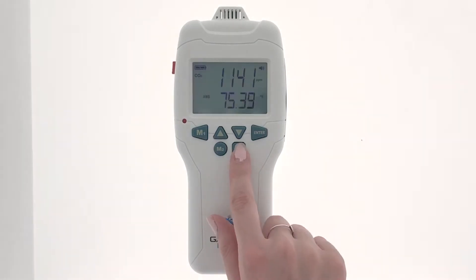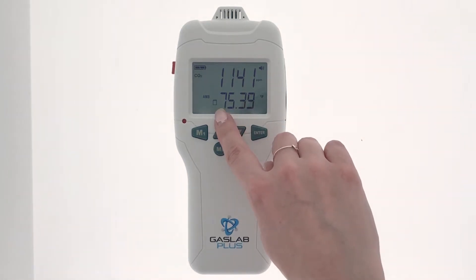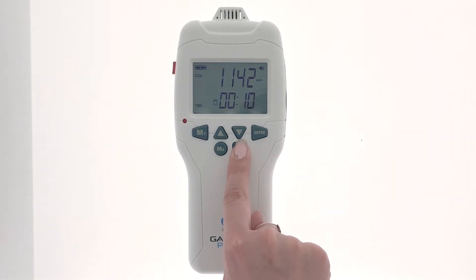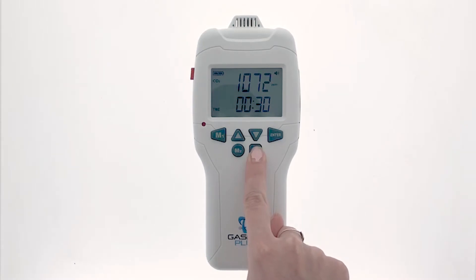You've got a 16 gigabyte SD card that comes with it to fill with all of your data — and trust us, that is going to be a lot of data. To start data logging, simply press and hold the log button until the icon of an SD card appears. When you're ready to stop data logging, press the log button for a longer period. If you're interested in changing the interval of your data logging, the CM501 defaults to take a reading every two seconds, but you can hold the log button for three seconds to increase the time between readings up to an hour.